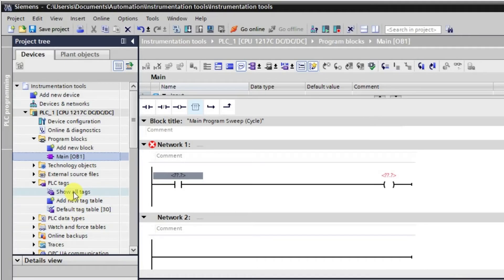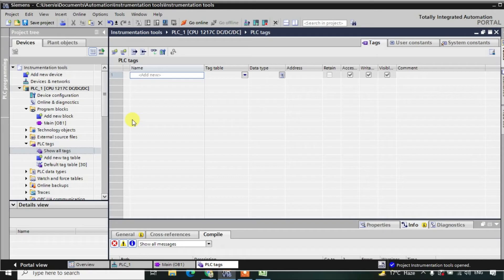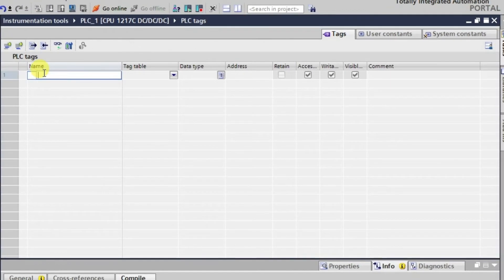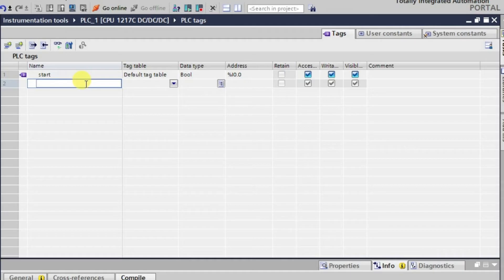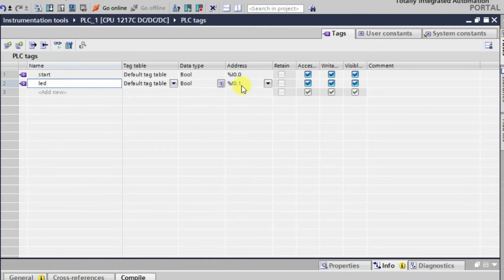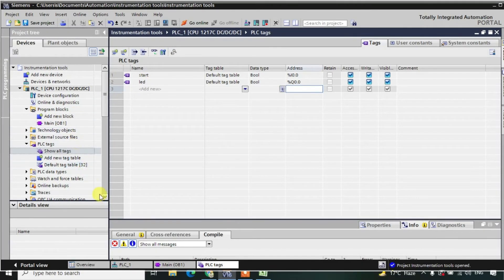We can go to PLC Tags and open the tag table, or just click on Show All Tags. Initially we have no tags, so we'll define some. The first tag is the input, named 'start', and automatically the address comes as I0.0 with data type Boolean. The second tag is the output, named 'led', and I'll change the address to Q0.0. Now both tag names are defined.